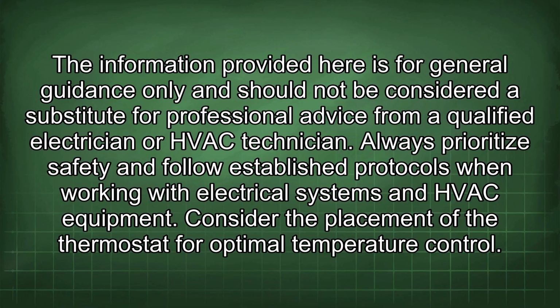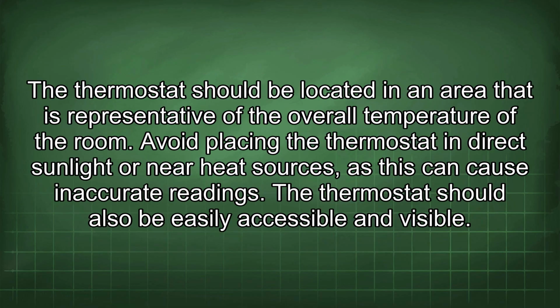Consider the placement of the thermostat for optimal temperature control. The thermostat should be located in an area that is representative of the overall temperature of the room. Avoid placing the thermostat in direct sunlight or near heat sources, as this can cause inaccurate readings. The thermostat should also be easily accessible and visible.